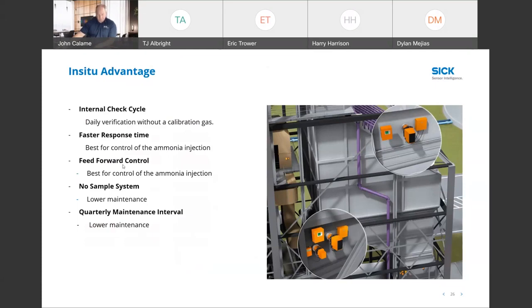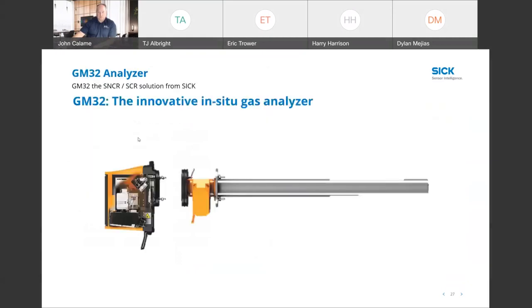But the nice thing is the speed of response. We're not conditioning or changing the sample, and there's no sample system on it. And the maintenance and the install cost is typically lower than an extractive system. So the GM32, which we would use as an in situ device and analyzer, can measure up to 4 components simultaneously. So it can do NO2, ammonia measurement, as well as moisture. This is the single probe design. So it's single penetration into the stack.